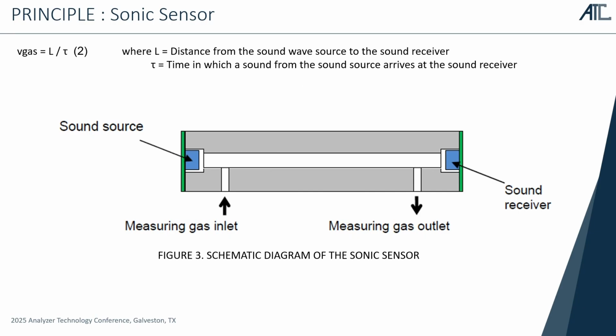So this is about the sonic sensor. Again, this sensor is to measure the sound speed of the target gas. And the same as the optical sensor, we know the relationship between the sound speed and the BTU value. So if we measure the sound speed, then we can measure the BTU value. And then here is a chamber, and the measuring gas is filled into the chamber here. And there is a sound source here. This is a sound receiver. So sound is emitted from here to here.